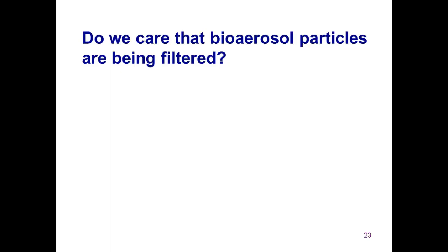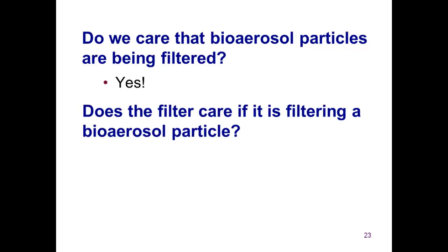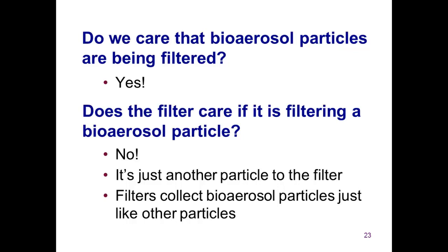Do we care that biological particles are being filtered? Of course, because they can carry disease, we care that they are being filtered. Does the filter care if it is filtering a bioaerosol particle? No. To the filter, a biological particle is just another particle that obeys the laws of physics. As long as particles have the same diameter, they are collected with the same efficiency, whether they are biological or non-biological particles. So, to answer the question from several slides ago, filters do collect bioaerosols.